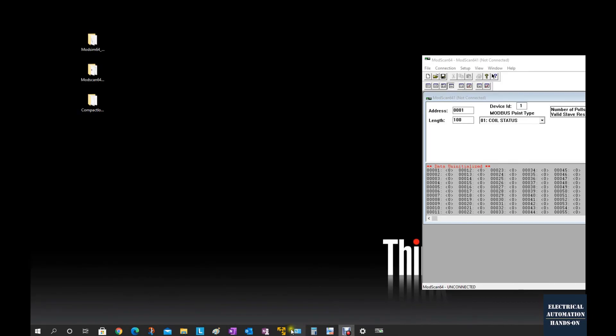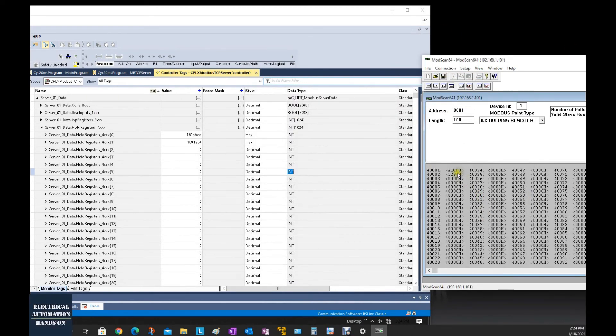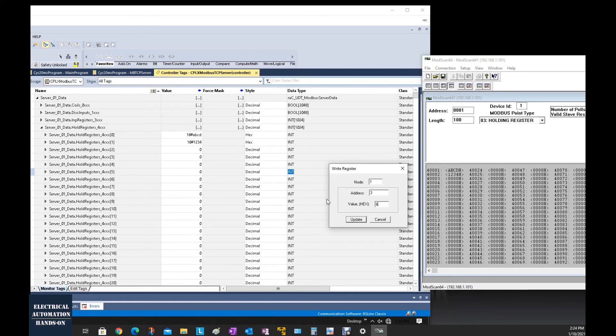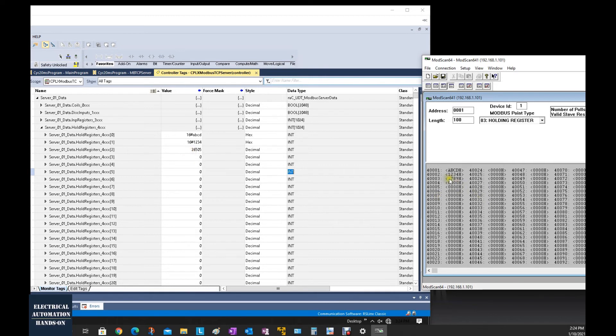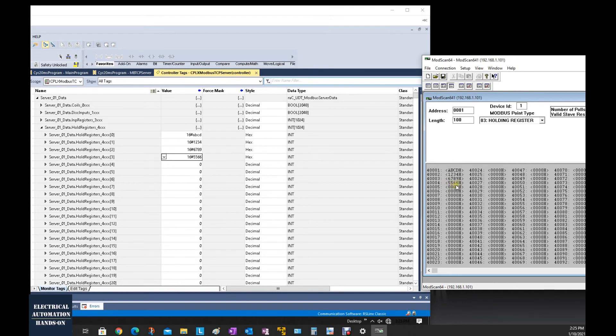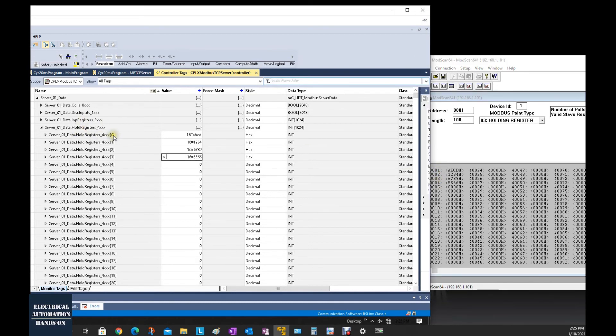After restarting ModScan, now it's connected. This time we can see the data. We sent ABCD — ABCD is received here. Then 1234 is here. If I click next and send 6789 hex, it's sent and received here. Switching from decimal to hex, we can see it is received correctly. If I change the number — for example, switch to hex and enter 5566 — we can see hex 5566 received here. One important thing to note: the Modbus address starts from one, but from the PLC side the index starts from zero — so there is a one-register offset we need to be aware of.